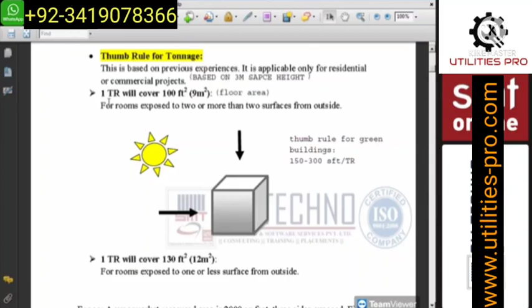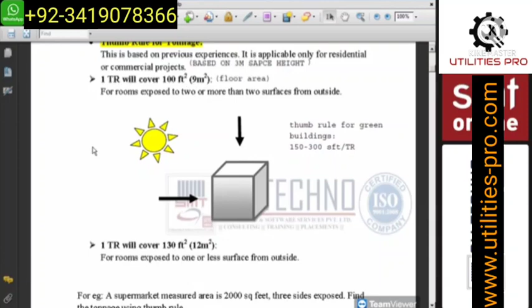Previously people asked only the thumb rule for a standard project, but now in the market, and at the time of interview, they are asking about green buildings also. So for green building, 1 ton will cover up to 300 square feet, a higher area, because the heat transfer is less in the green building, as we are designing the construction with good insulation. Okay. And this is important from the interview point of view.